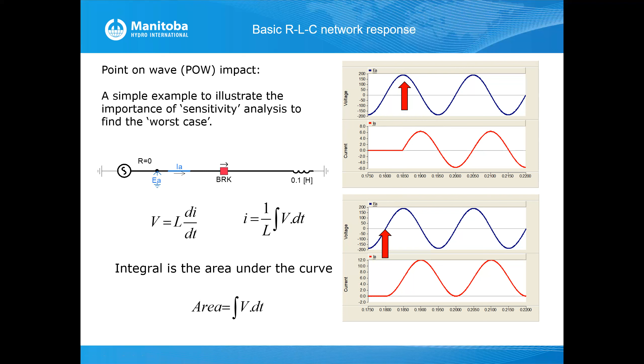Another very important reason why EMT is important is when you look into the network, okay, let's say you have a very simple system comprised of two parts like this. And when you interrupt the circuit by opening the breaker, and then look into the system, what you'll find is that there is a resonant point, a parallel resonant point. In this case, there's a parallel resonance at a frequency of 600. So there's the 12th harmonic, okay? Just after the 12th harmonic, we have a parallel resonance.